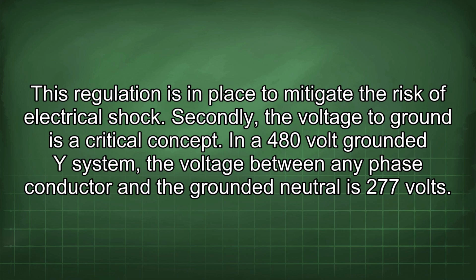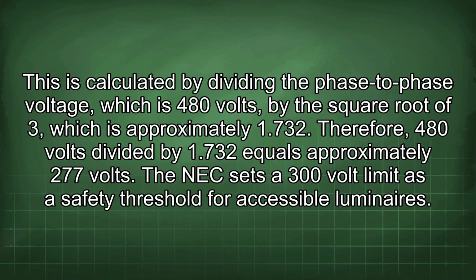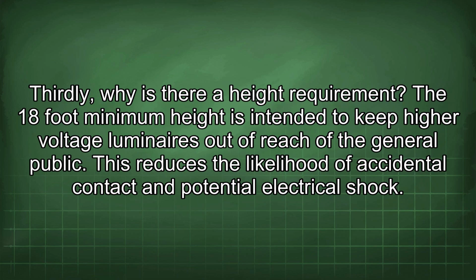Secondly, the voltage to ground is a critical concept. In a 480-volt grounded Y system, the voltage between any phase conductor and the grounded neutral is 277 volts. This is calculated by dividing the phase-to-phase voltage, which is 480 volts, by the square root of 3, which is approximately 1.732. Therefore, 480 volts divided by 1.732 equals approximately 277 volts. The NEC sets a 300-volt limit as a safety threshold for accessible luminaires. Thirdly, why is there a height requirement? The 18-foot minimum height is intended to keep higher voltage luminaires out of reach of the general public. This reduces the likelihood of accidental contact and potential electrical shock.